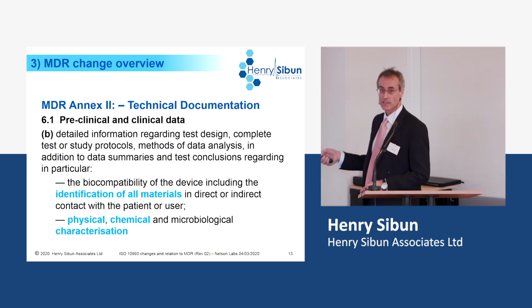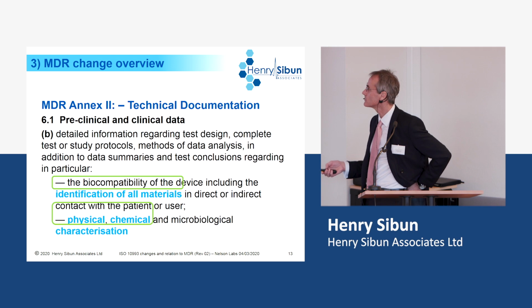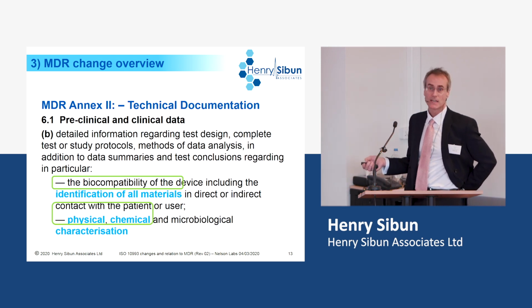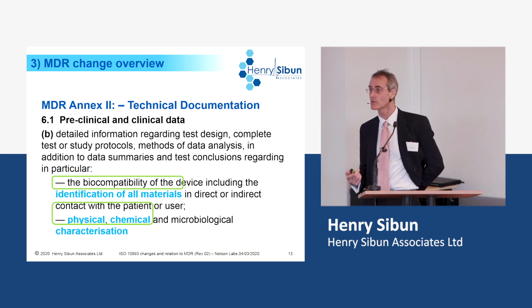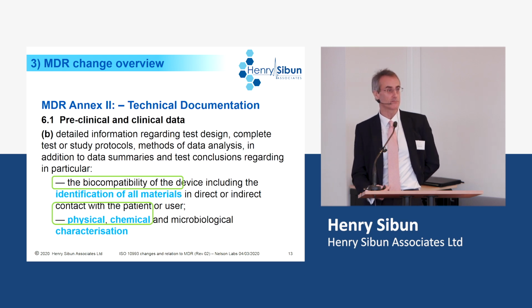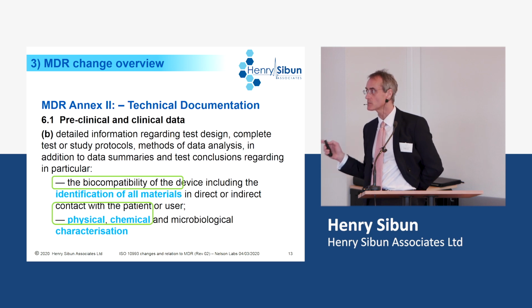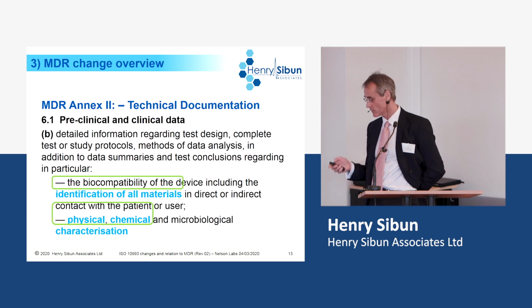And there's a big list of things. I've only put the biocompatibility ones here. So we've got biocompatibility, so identification of, these are of materials, and in particular, the physical and chemical characterization. And again, this is pushing back the big focus in this regulation. You need to know what you're dealing with. Because in theory, if you know what chemicals you've got, you can judge those risks without needing to do testing. It's maybe not quite as simple as that in practice, but there's a big emphasis on you maybe doing some actual leachable and extractable studies and for doing a proper literature search to find information on the safety of these.